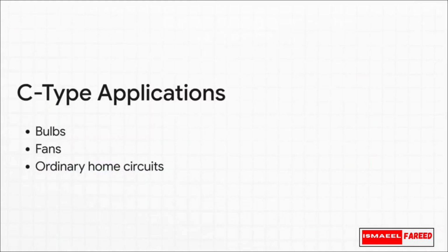To put that into a real-world perspective, you actually use these all the time. Common applications are your standard bulbs, your ceiling fans, and just ordinary, everyday home circuits. When you flip the switch for a ceiling fan, the motor needs a little extra juice to get those heavy blades spinning from a dead stop. The C-type breaker is smart enough to recognize that medium surge as totally normal operation, so it lets it happen. This is the hardware you're interacting with the most at home.